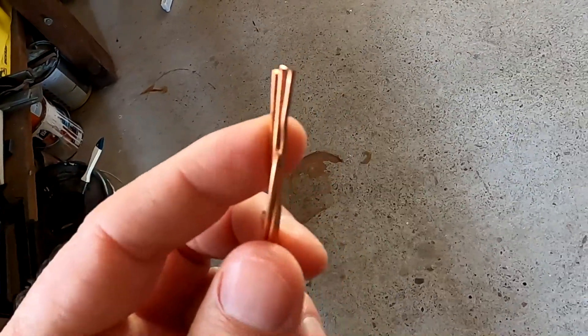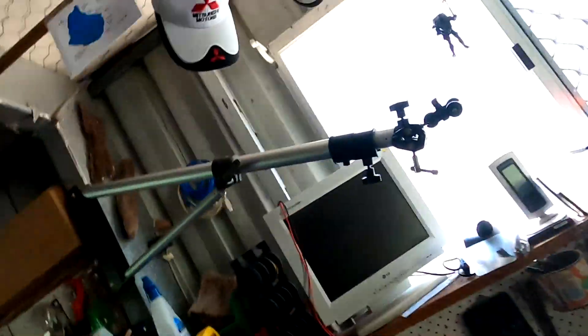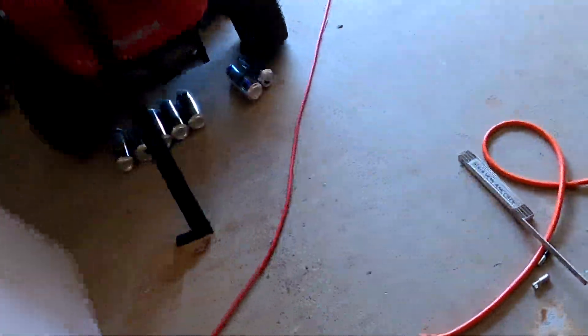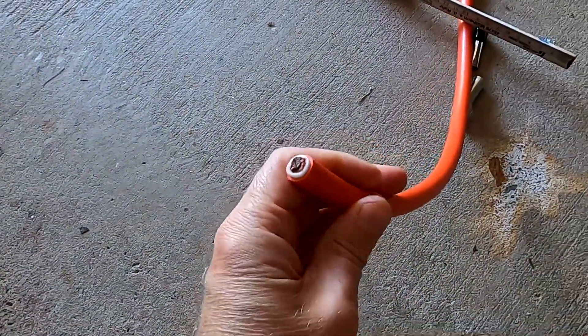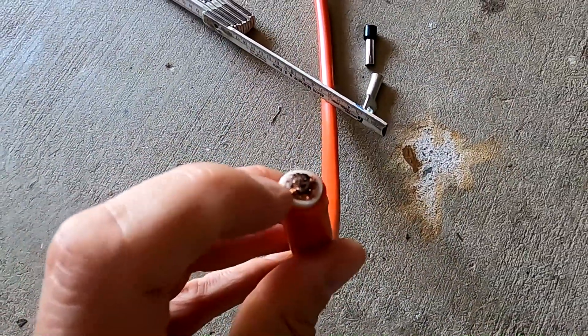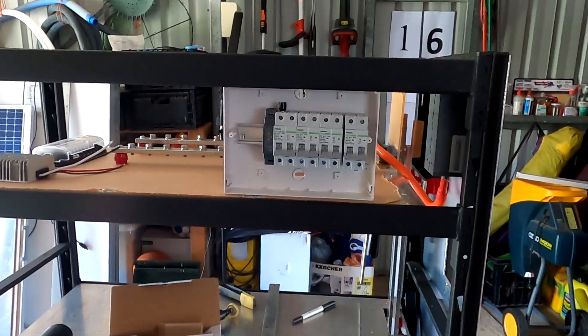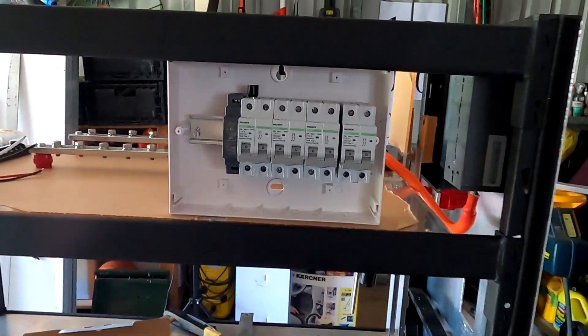If you have multi-stranded cables like these ones, they've got only five or six strands inside. Yes, you can connect them right into your terminals of your circuit breaker. Or if you have building wire which is just a single core, yes you can connect them straight. But not this fine stranded high flexible cable. Some of the wires may not even touch your terminals when you screw them down. The cable may squeeze out and become really flat, so effectively you are reducing your diameter of your cable size which could lead to heat.